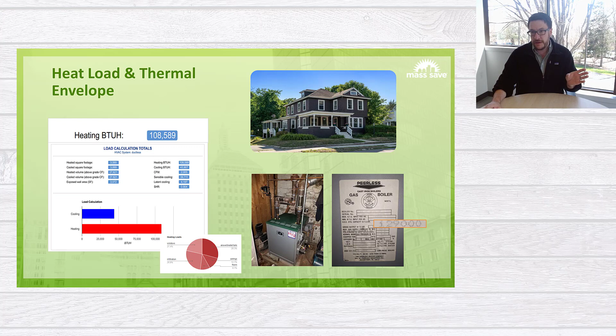For this home, when I put all of that information in, I found that the heat load for the home was 108,000 BTUs per hour. Now, if I were to be going down into the basement and I were to look at the steam boiler, I would see that the steam boiler has a heating output of 129,000 BTUs per hour. So the heating system is greater than the heat load. The steam heat works in this home. Now, let's just go and think about how Mass Save and heat pumps may correlate with this type of a home.